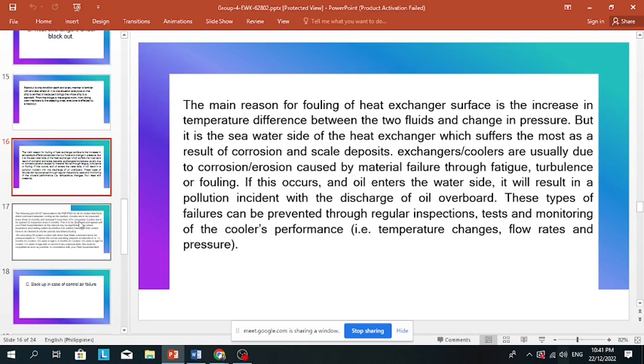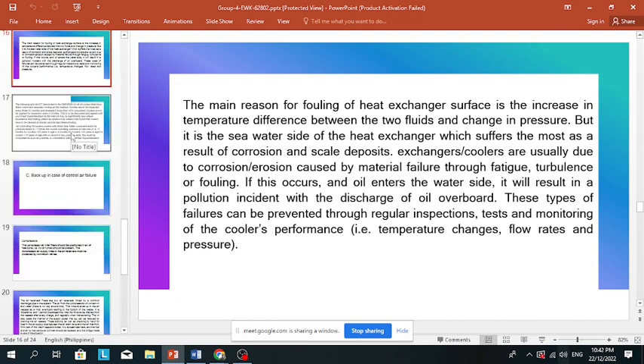The main reason for fouling of heat exchanger surfaces is the increase in temperature difference between the two fluids and in pressure, but it is the seawater side of the heat exchanger which suffers the most as a result of corrosion and scale deposits. Exchangers or coolers usually fail due to corrosion and erosion caused by material failures through fatigue, turbulence, or fouling. If this occurs and oil enters the water side, it will result in a pollution incident with a discharge of oil overboard.